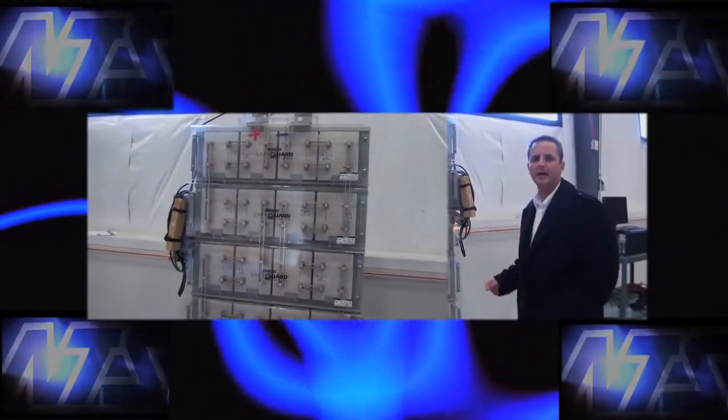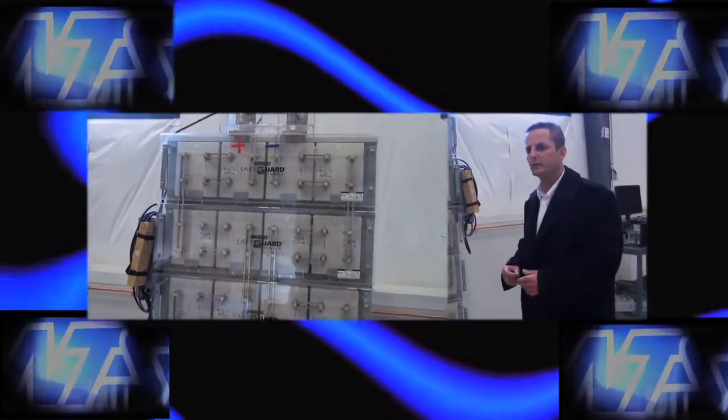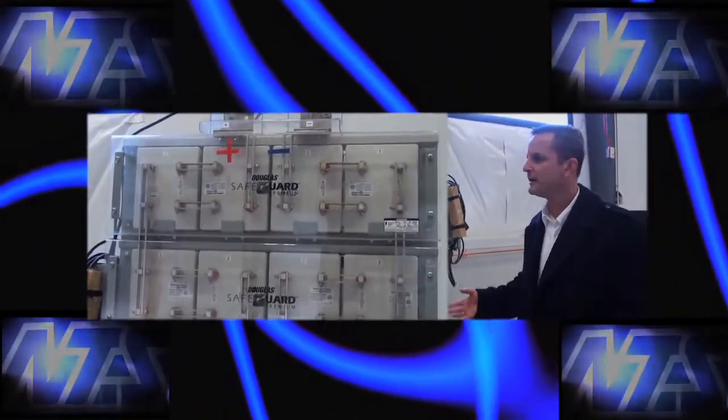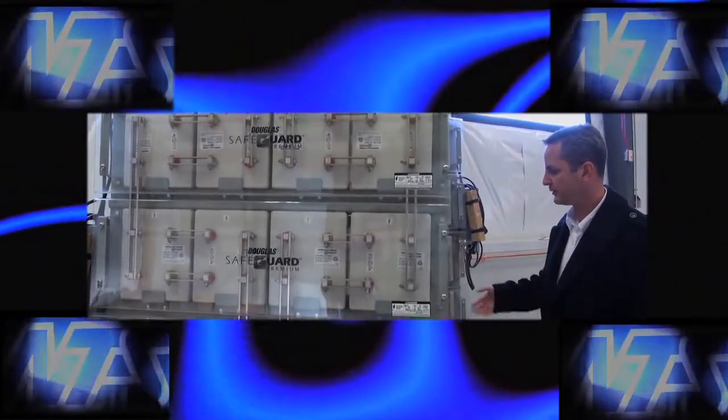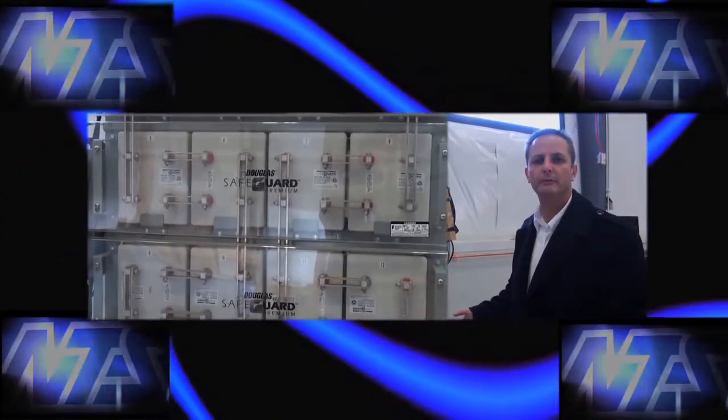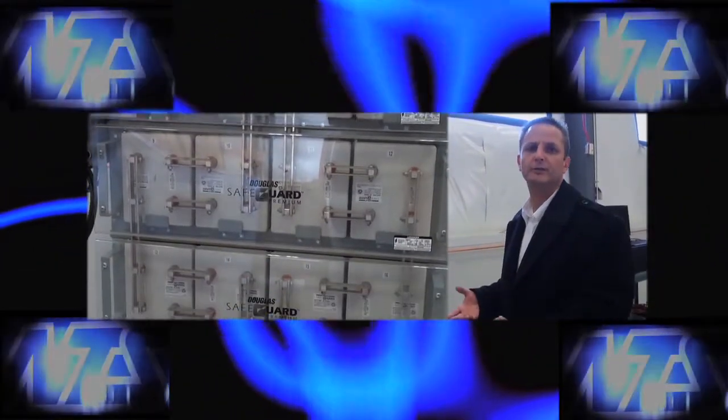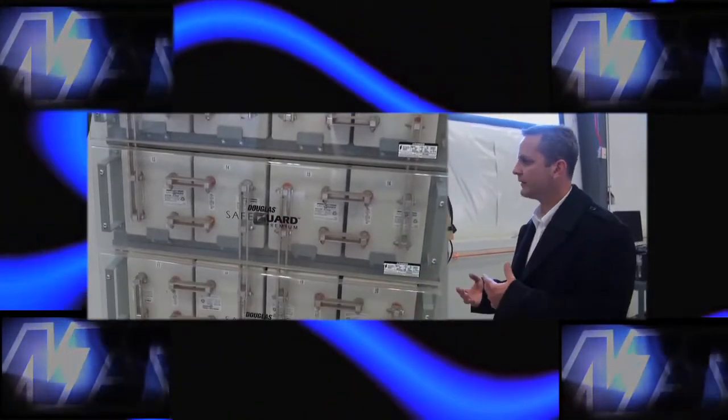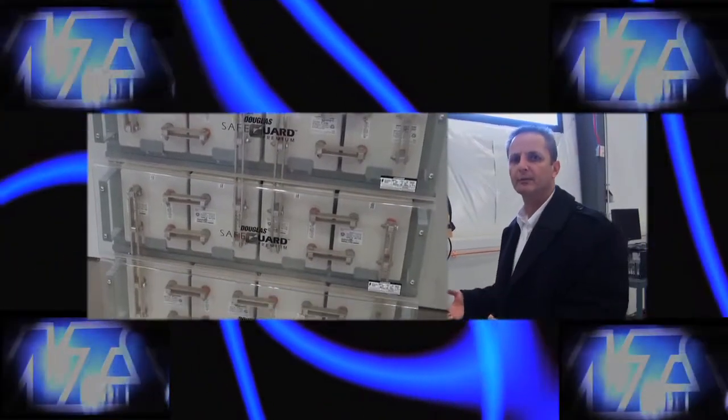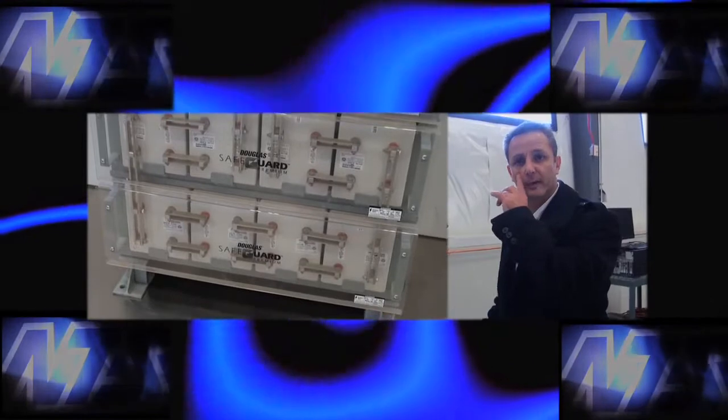This is our DC battery bank, mainly used for telecommunications testing. It's a series parallel matrix of batteries to produce minus 48 volts DC. This battery bank is capable of providing 3,000 amps for 8 hours at minus 48 volts.